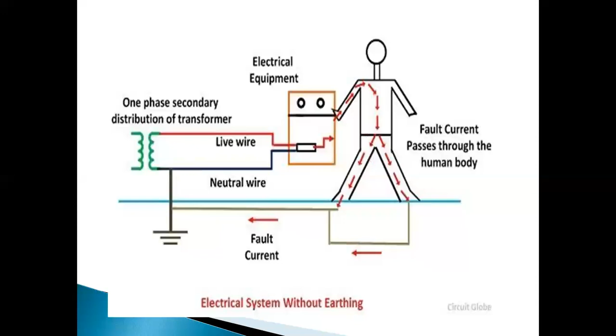The key difference between earthing and grounding is that earthing means the circuit is physically connected to the ground, which is at 0-volt potential relative to earth. Whereas in grounding, the circuit is not physically connected to ground, but its potential is 0 with respect to other points.